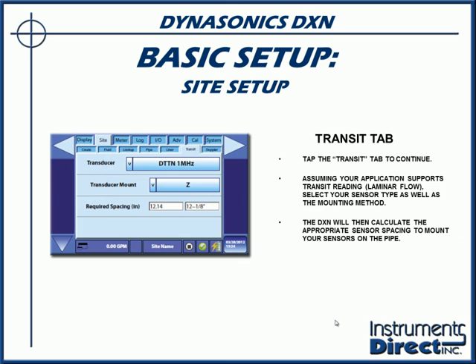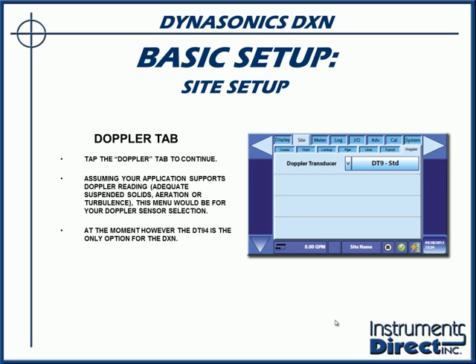So it's very intuitive. You're not typing in the sound speed of water, 4,900 feet per second. You could if you wanted to. You're just putting in water. So it's doing the calculation for the water. It's doing the calculation for the carbon steel pipe and so on. So here's our spacing. It's 12.14, or 12 and an eighth of an inch. That would be the differential between the two transducers when you mounted it.